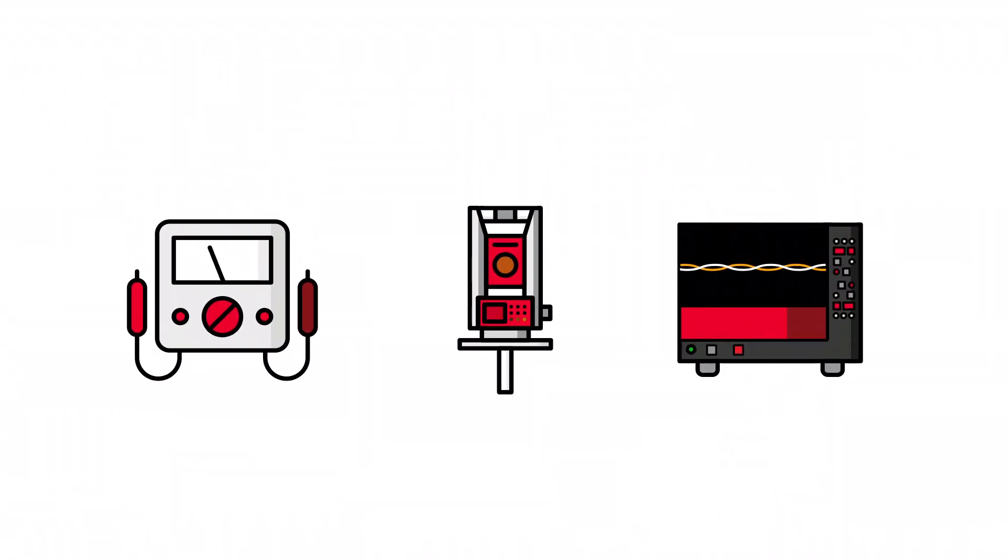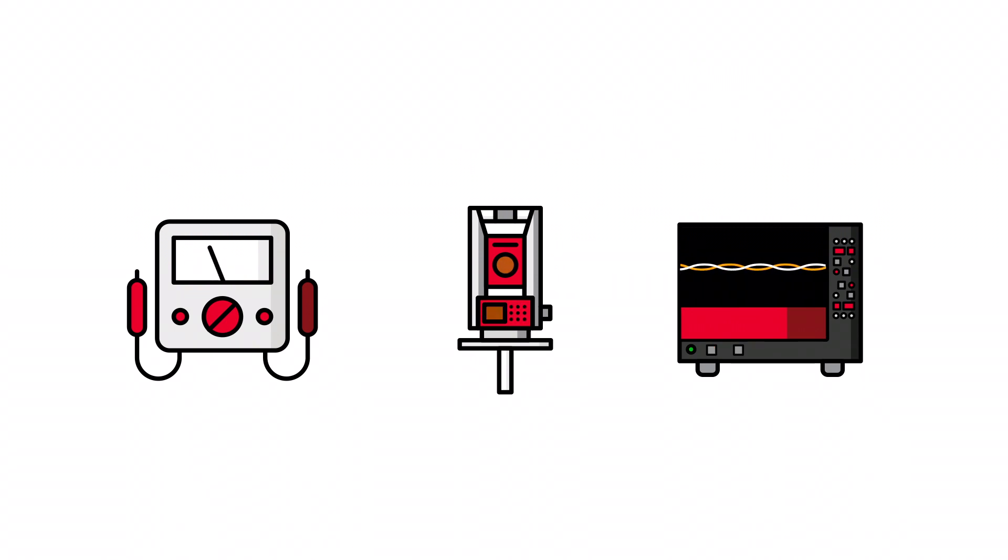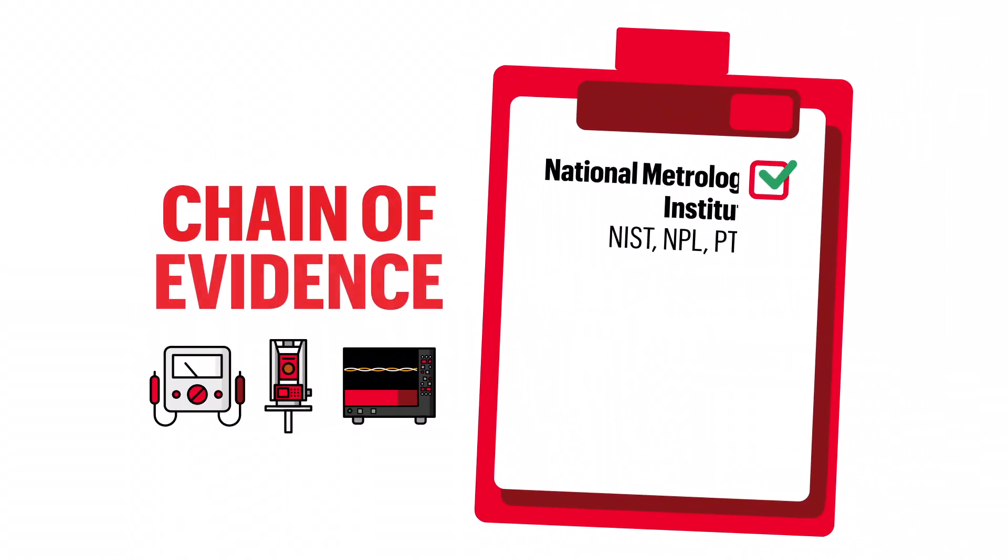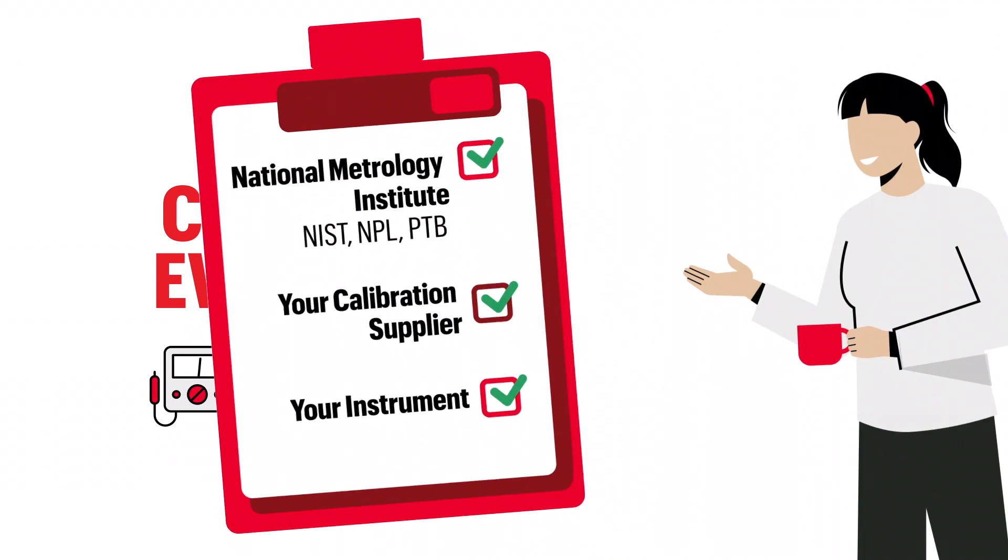For instruments, traceability represents the credibility of measurements. Is your supplier's lab equipment maintained and calibrated in a fashion traceable to a recognized national reference? Every supplier should provide the chain of evidence to prove this, but not all do.